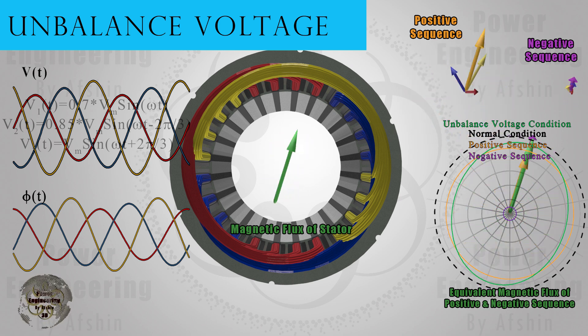However, if the voltage imbalance is such that one of the phases has a voltage higher than the nominal value, magnetic saturation may occur at the stator.